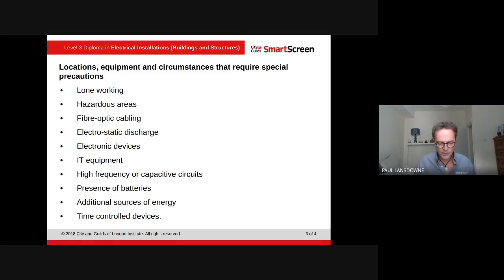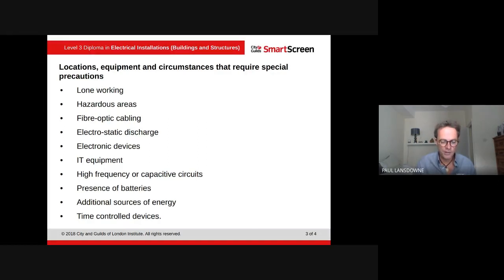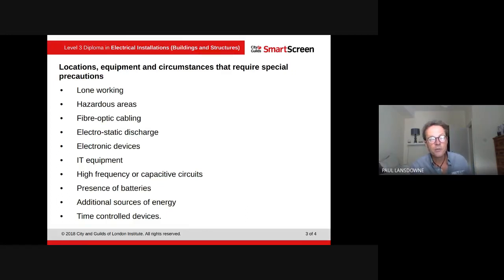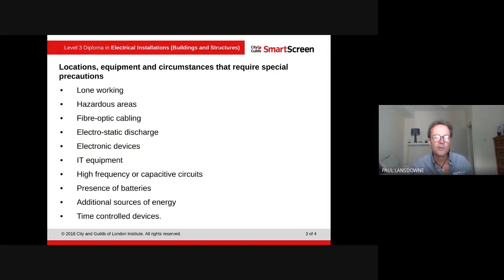With electronic devices you've got to be really careful when using high voltages. If doing insulation resistance testing, make sure it's on the right setting. Back up data before taking any power off, and be careful about battery backup — when you isolate a circuit thinking it's dead, the battery backup may have kicked in and made that circuit live again.